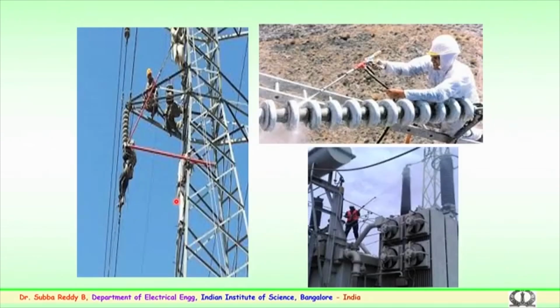These are some of the practical conditions where de-energized cleaning is being carried out. You can see here in the tower arrangement for a single suspension string, the utility people physically clean the insulator by hand washing methods, as over a period of time the contaminants accumulate on the surface and become hardened.